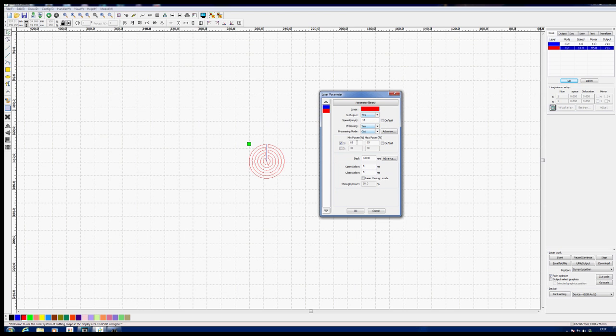So when it comes to running power tests, you will be in control. You'll set the minimum and maximum power to a series of values so you can calibrate your machine. In other words, you'd set this initially to maybe 10, then 20, 30, 40, 50, all the way up to 100%, by editing it on the machine and running the test.